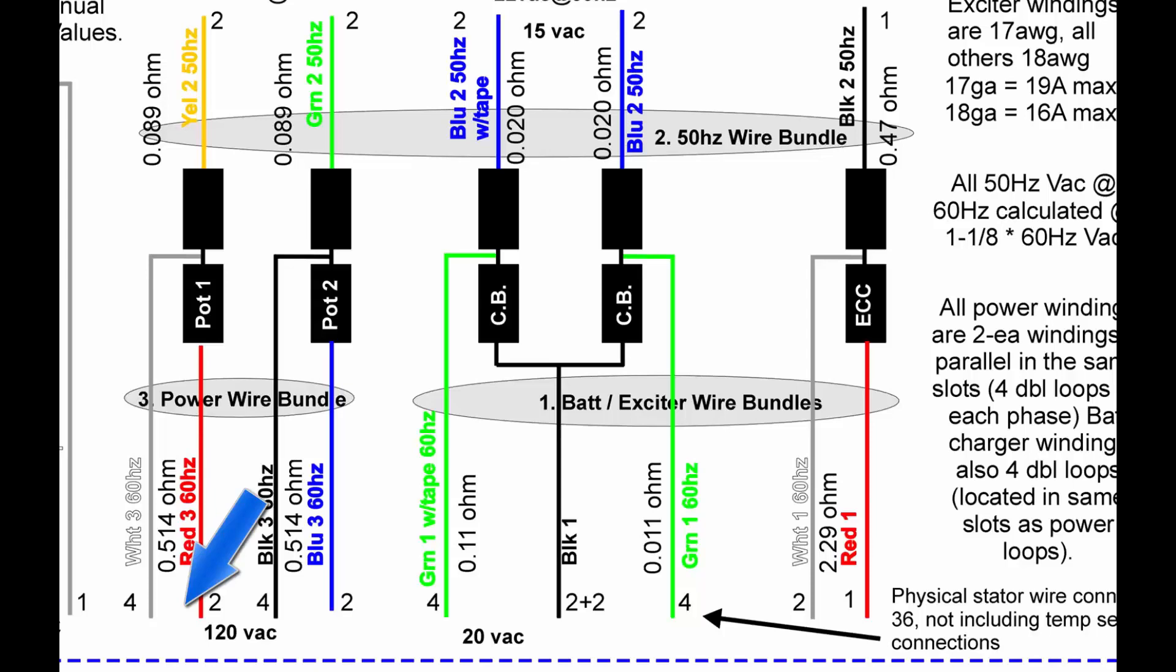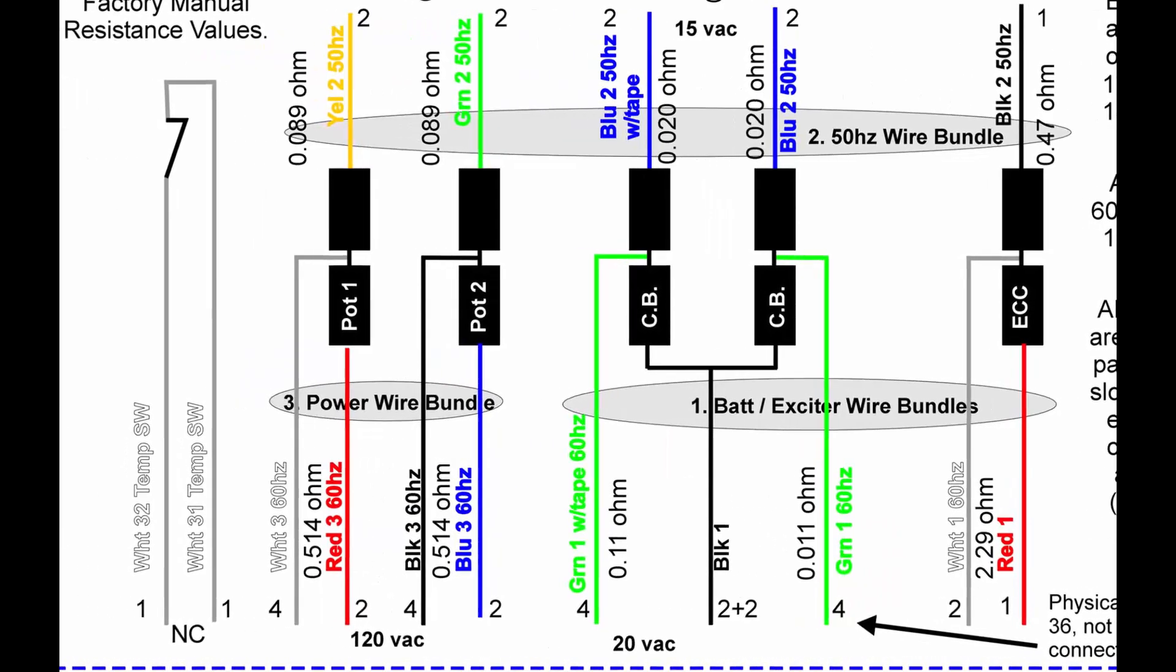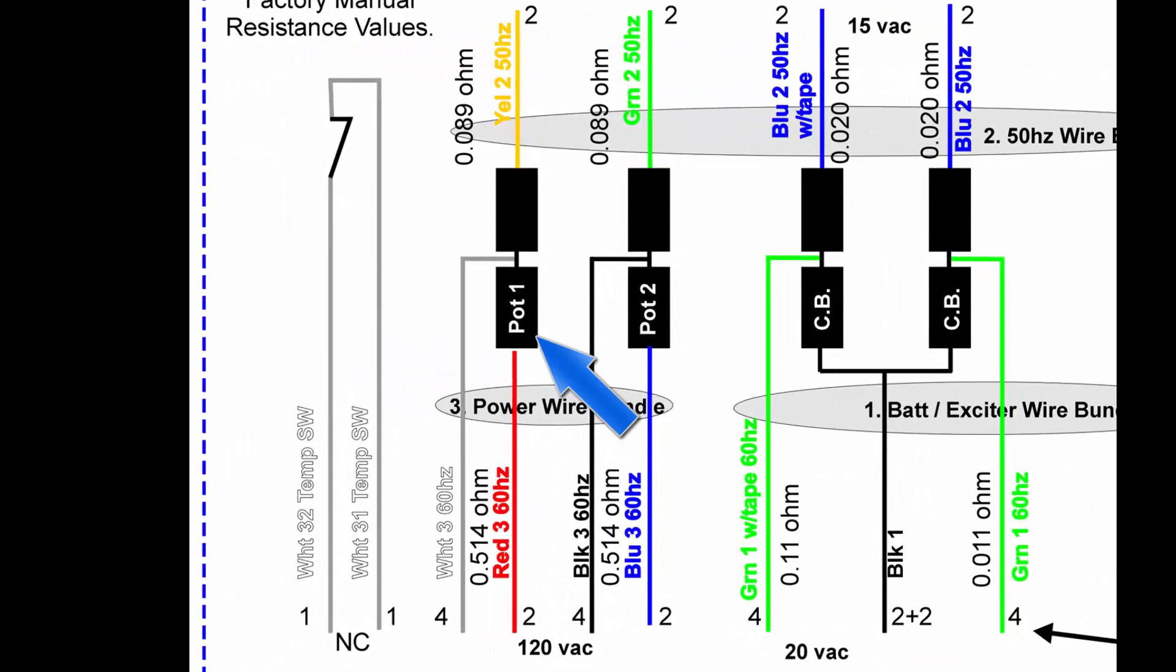For example, pot one is one phase and pot two is the other phase of the primary power windings. If you look at pot one for a minute, the red three at the bottom, when it's connected to the white three, generates 120 volts AC.